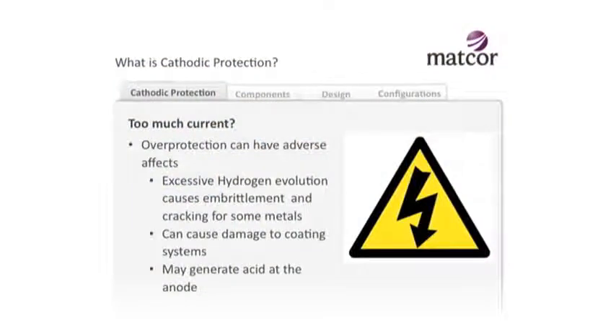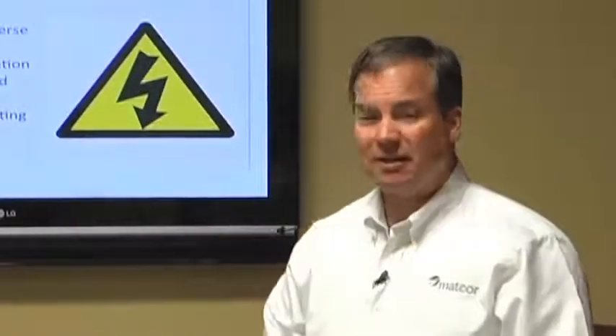The key concept is: how do I know I have enough current to protect that structure? We also talked about too much current - overprotection can have some adverse effects, especially for certain metals like stainless steels, titanium, and other exotic metals. For carbon steel, it's virtually impossible to put too much current on it. But there's a practical issue: at some point you're just wasting current. Once it's protected, why throw a lot more juice onto it? So while carbon steel is pretty immune to overcurrent, there's a practical aspect - it doesn't make sense to put too much current onto it.